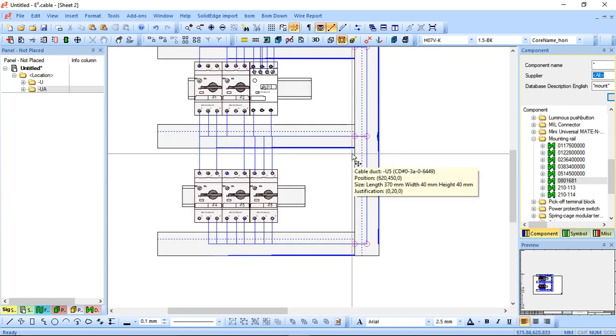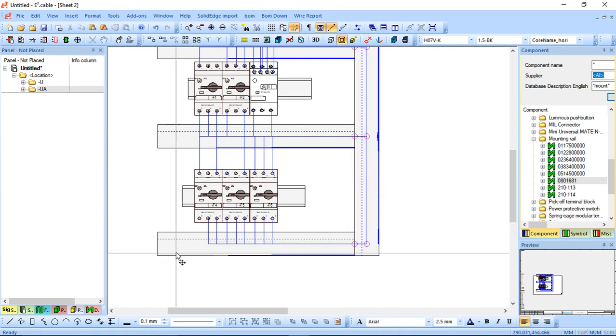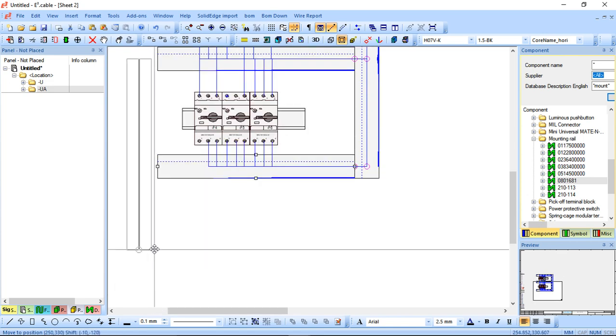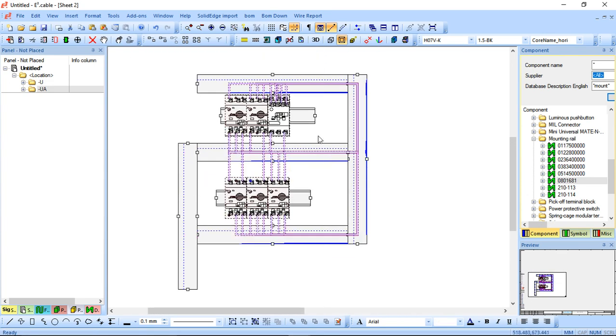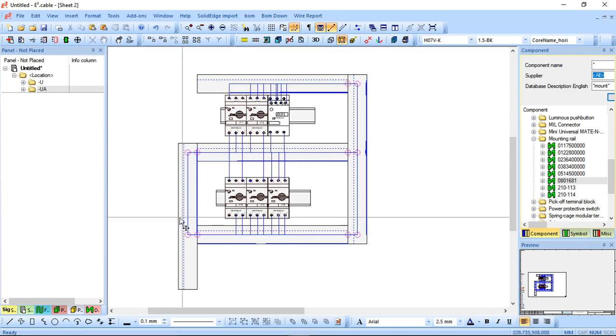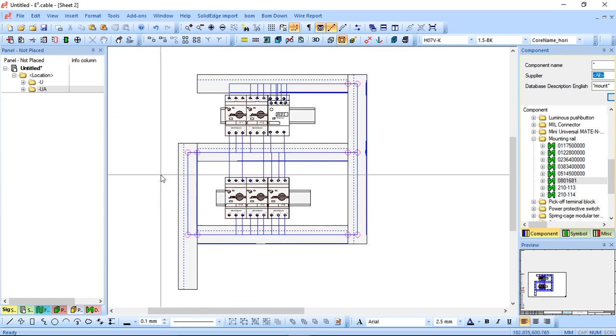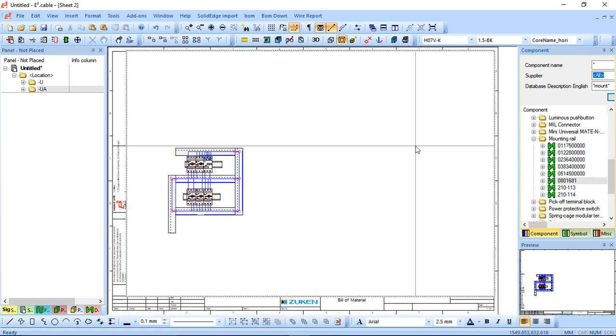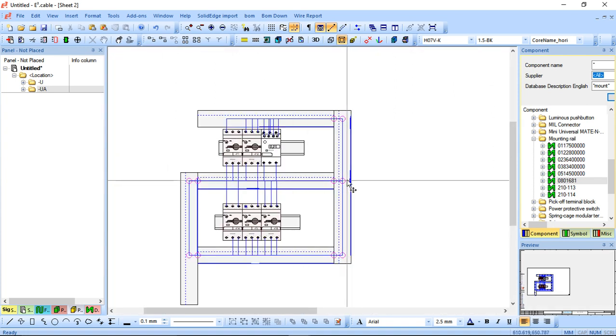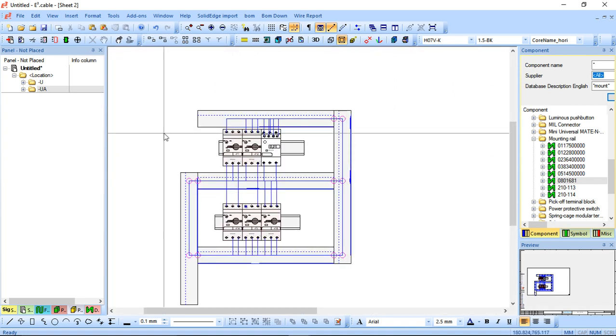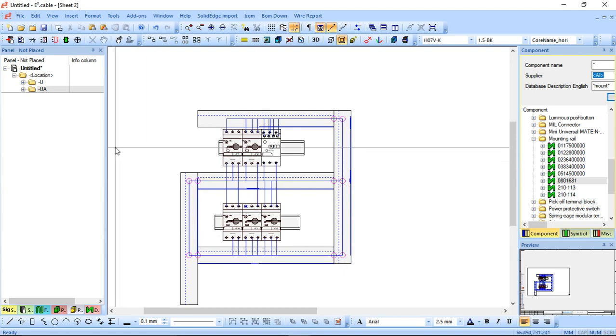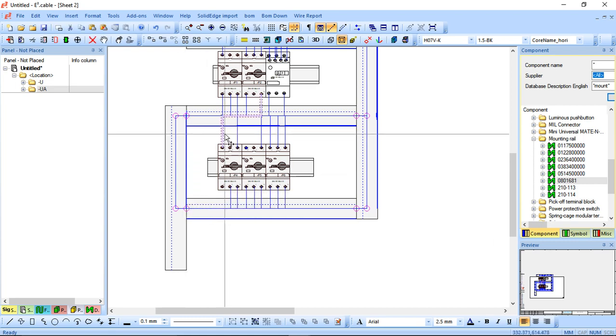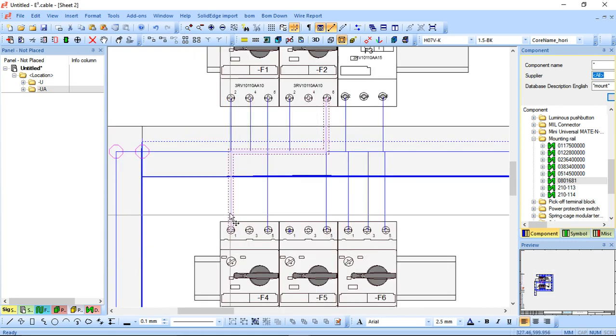You can see now it's automatically routed all these connections based on the schematic. It's actually done it to the shortest distance as well. So if I had another duct on this particular side and once again selected everything, it would actually route it to the shortest path — the path of least resistance. Similarly speaking, the blue thickness represents the thickness of the cables within the duct. So once that duct does fill up, it would actually seek to route it in an alternate path. It does have a fair bit of failsafe. Now that it's done automatically, this is to scale, so I can select a particular cable and you can see it highlights — it's just going from there to there.